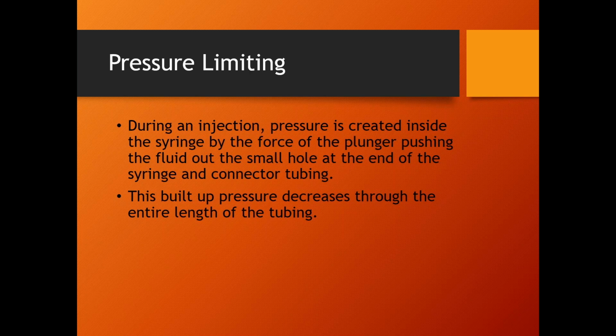Now keep this in mind though, and this is a confusing part for some operators. That 300 PSI is not a goal, okay? If I select a flow rate of 10 and a volume of 20, yes, when we do the injection, I want the flow rate to be 10 milliliters per second, and I want the injection volume to be exactly 20 milliliters, and then it ends, all right? But if I select a pressure limit of 300 PSI, all we're saying is don't exceed 300 PSI. If during the injection we only get up to 20 PSI, that's fine, all right? We're just saying don't go over this, okay?